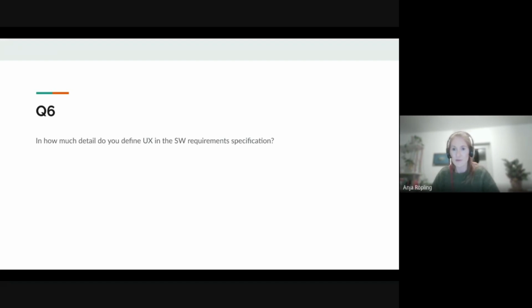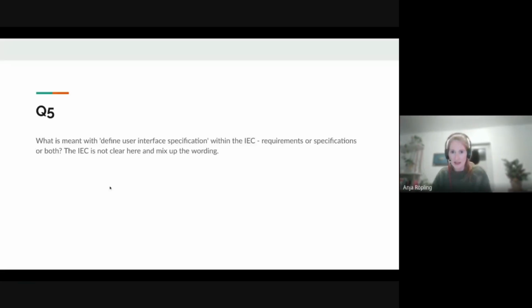Also just for best practice, because sometimes it happens that you say, okay, we want to have it green, and then you do usability testing and check if the user understands what green means. And then during the next project, some developer has the idea that maybe yellow or pink would look nicer. And then suddenly you have one of your risk measures that you mentioned in the risk analysis not there anymore. So that's something that I would definitely specify.